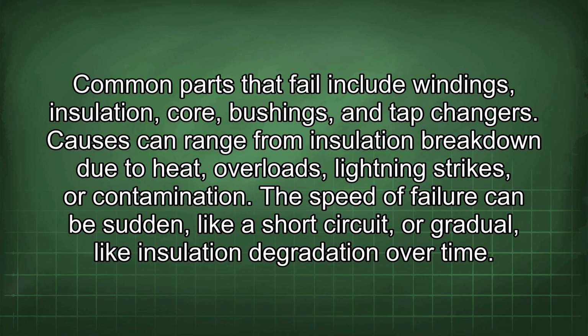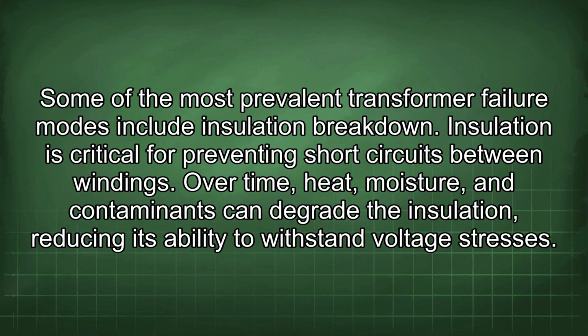Common parts that fail include windings, insulation, core, bushings, and tap changers. Causes can range from insulation breakdown due to heat, overloads, lightning strikes, or contamination. The speed of failure can be sudden, like a short circuit, or gradual, like insulation degradation over time. Some of the most prevalent transformer failure modes include insulation breakdown.